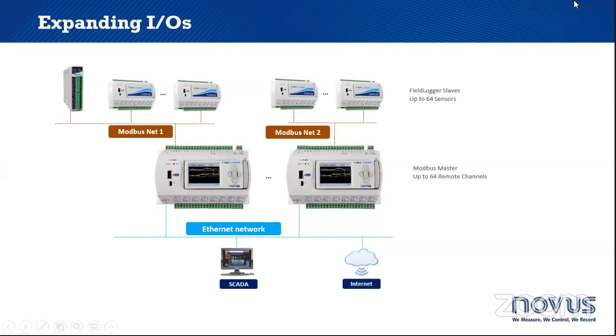Also a very important detail here is the field logger has an economic version, okay? Which is a unit that doesn't come with Ethernet, doesn't come with memory expansion, and doesn't come with HMI connection. So it's a short version of the field logger, but it works very well as an IO module. So if you're thinking of expanding your actual field logger possibilities or channels, you connect it via Modbus to a low cost field logger version. Okay. If you only want to use it as a standalone logger, not connected to anything, well, the low cost version can also work for you as a data logger. Okay. Also important one here, DigiRail Connect is our latest release on IO modules, Modbus IO modules. Have a look at that as well. Okay.